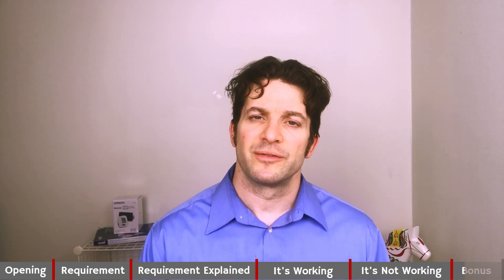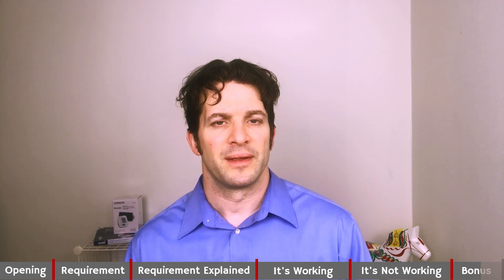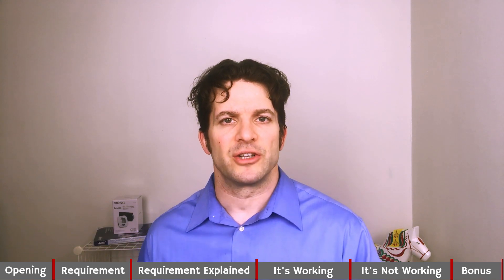Now, for the three bonus questions. Do we have a line clearance process for clearing out all materials before we start the next manufacturing run? If yes, what's the procedure number? Second, do we do label reconciliation? Third, how do we capture the actual labels within the DHR?